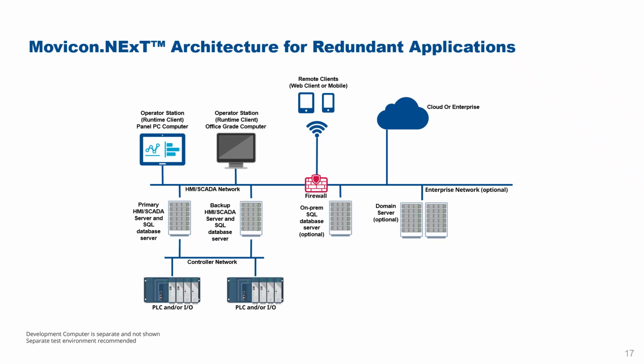For redundant applications, it's effectively the same architecture we saw before, except now you have an additional computer for redundancy. We support N+1 redundancy, but in a basic redundant application, which covers most cases, it's 2 computers: a primary server, normally your master, and a backup computer. The backup takes over when the primary fails, or more likely these days, when the primary is power cycled after installing an operating system update.